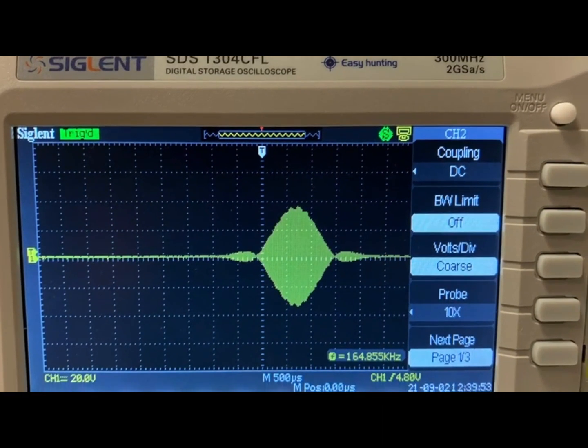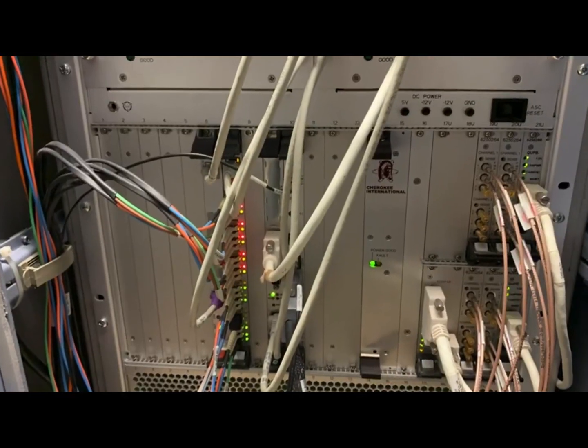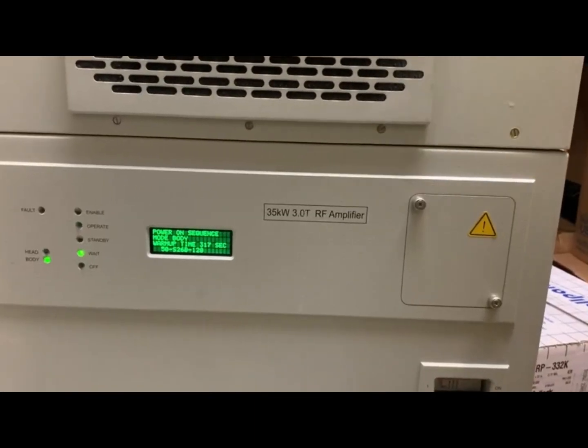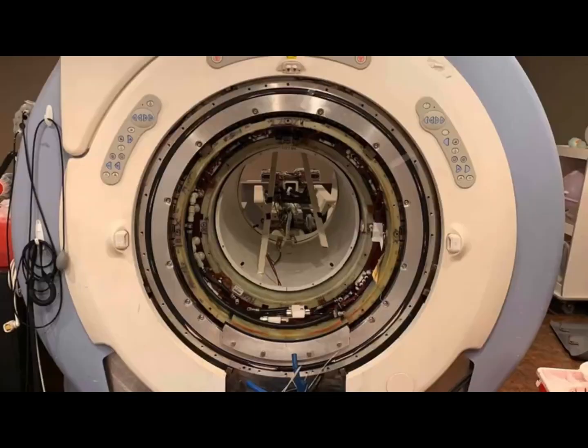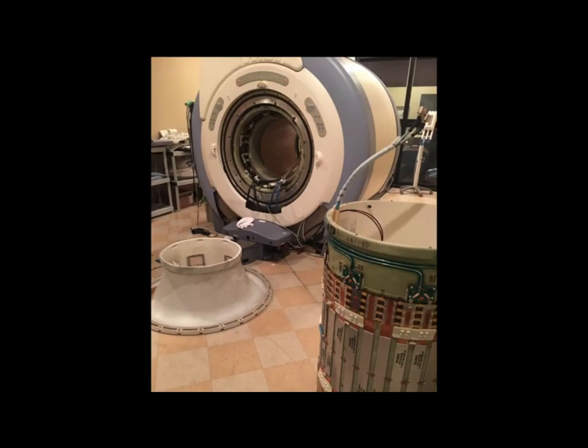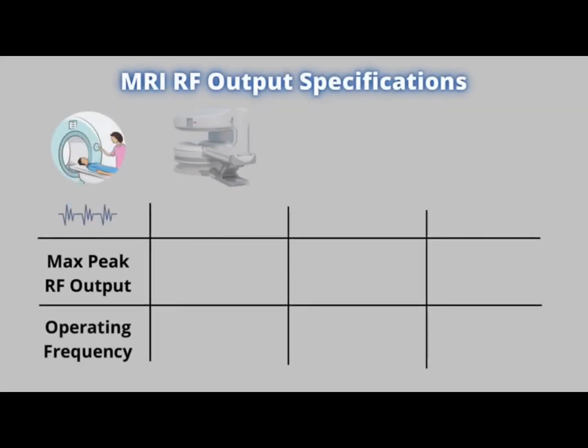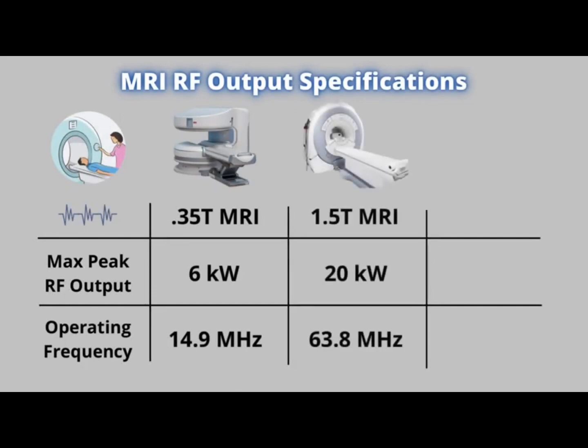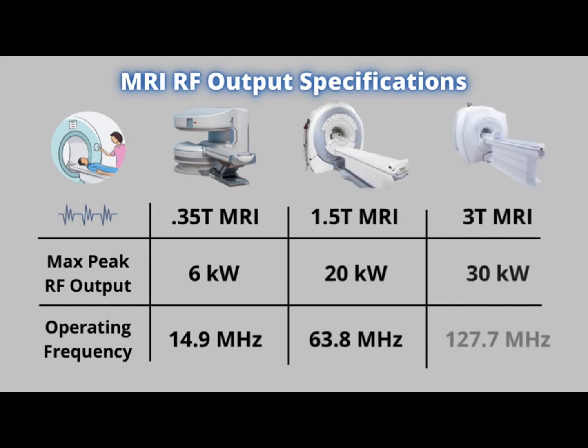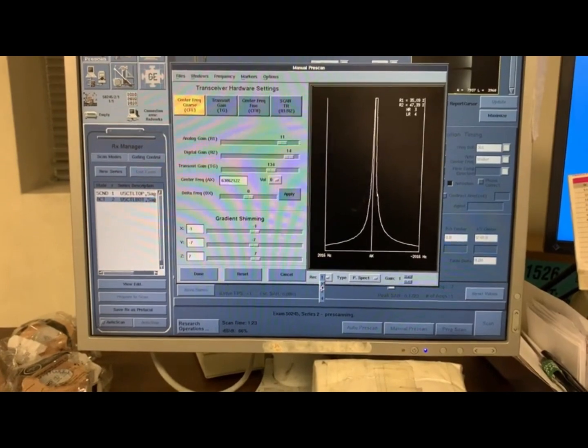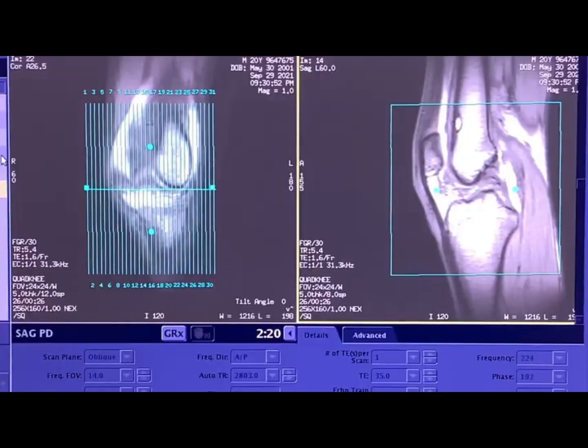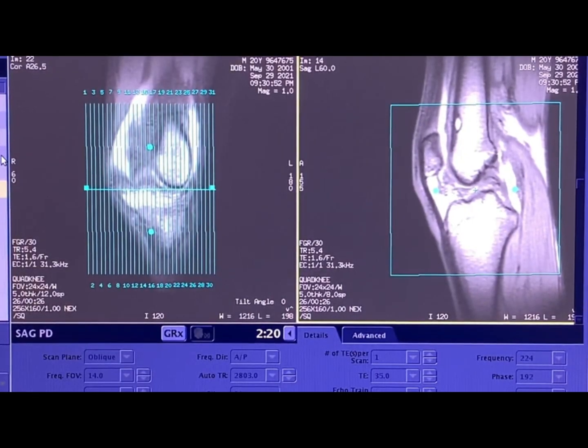MRI sounds begin as a small RF source signal of less than 5 volts produced by the exciter assembly in the MRI system's cabinet. The radio frequency pulse makes its way to the RF cabinet where the signal is amplified and directed into the RF coil. The sounds of one machine may differ from another because the operating frequency and RF power output required varies according to the strength of the magnetic field — higher magnetic fields require more RF output at a higher operating frequency. The RF coil inside the MRI scanner acts as a speaker and transmits the amplified RF signal at the angle prescribed by the MRI technologist.